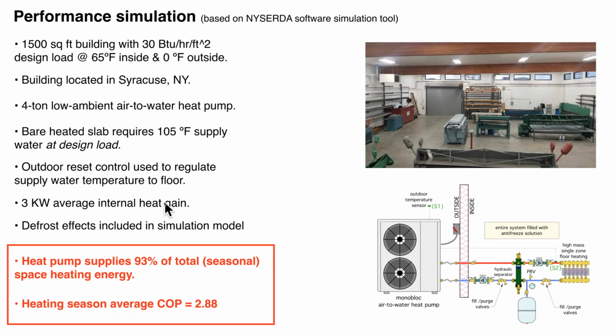Any type of air source heat pump in a cold climate has to go through defrost cycles. It's going to build frost under certain atmospheric conditions, and we have to defrost that unit. That does require energy. Basically, you're putting the heat pump temporarily into cooling mode, and you're using the hot gas to melt the frost. Well, what we found with these specific inputs was that the heat pump was supplying 93% of the total seasonal space heating energy, and our average COP, coefficient of performance, for the winter was 2.88.